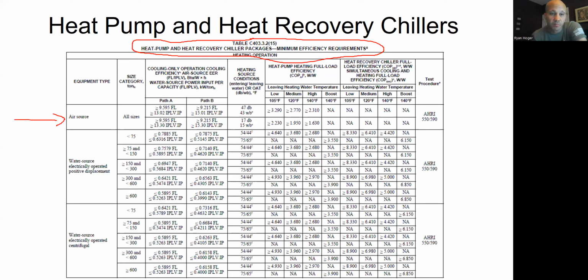Water source, positive displacement compressors. Water source, centrifugal compressors. Those are the two kinds of compressor divisions we have for regular chiller efficiency tables. So they've used those same divisions for these. So you do that, and then depending on that, you look at the tonnage you have. For air source, the rules are the same for every size. For water source, there are breakdowns for little ones under 75 tons, 75 to 150, 150 to 300, and so on. And you look at it that way.